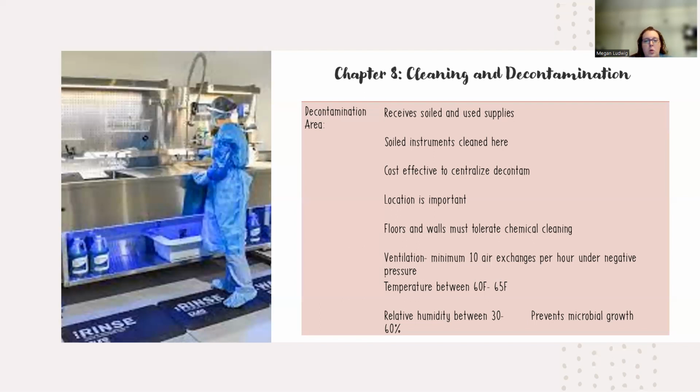So unique to the decontam, you have to have walls and floors that are going to withstand a lot of cleaning, because you're getting all those dirty things in. So they have to undergo a lot of chemical cleaning. So you wouldn't want wallpaper, those types of walls that don't wipe down very easily.